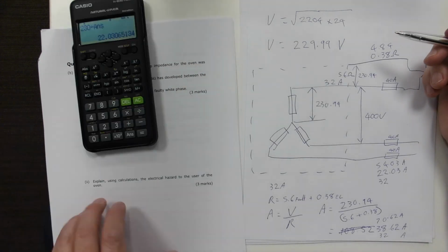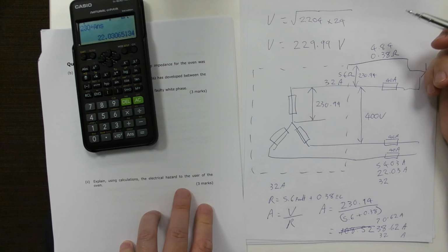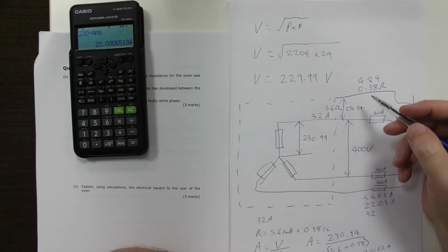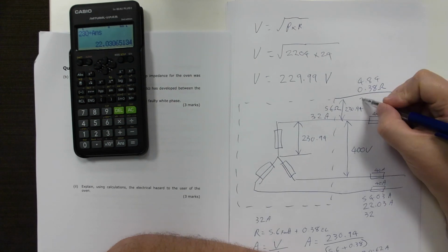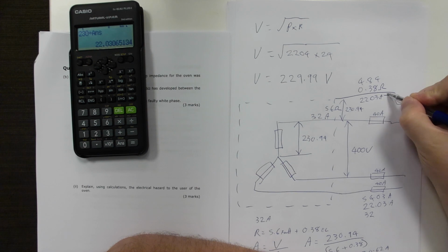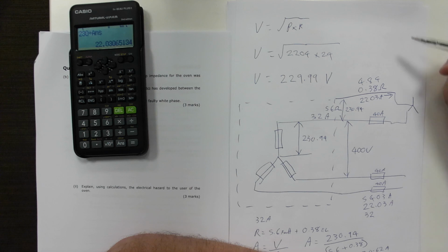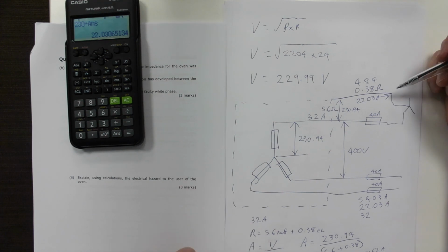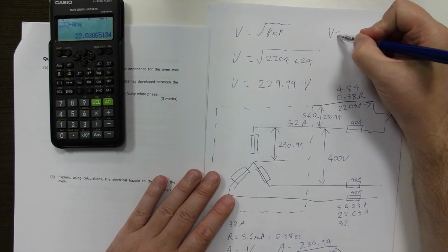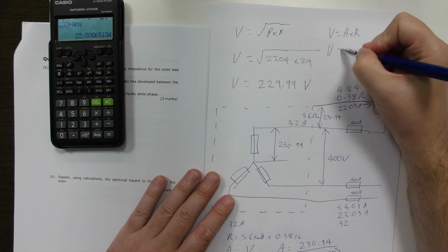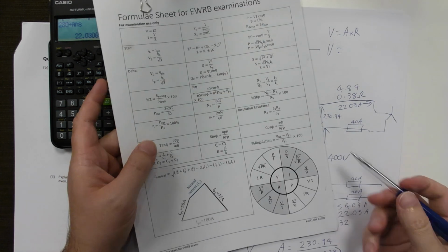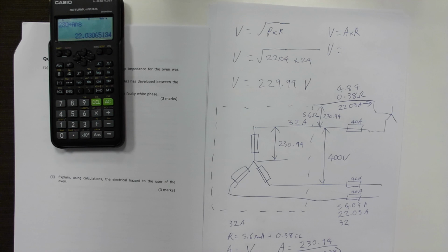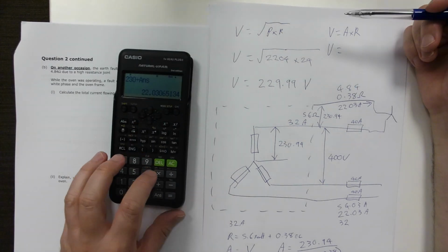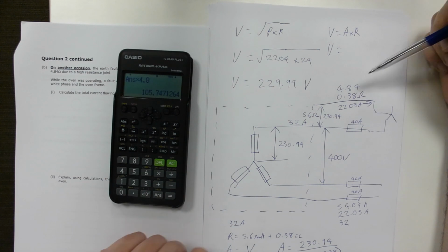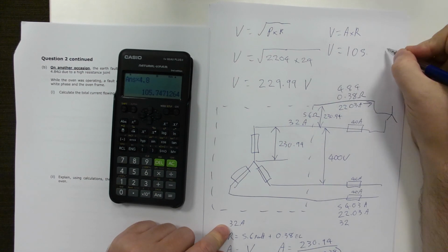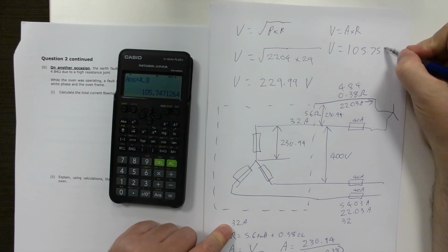Now, explain using calculations the electrical hazard to the user of the oven. So we have flowing through this wire here our 22.03 amps. So that's flowing down this wire back to our earth or any endpoint. The calculation we want to do is volts equals amps times resistance. So volts equals, and this is once again from our little wheel here, volts equals amps times resistance. We've already got the amps in the calculator, so times by our resistance, which is 4.8, and we end up with 105.747, so 105.75 volts.